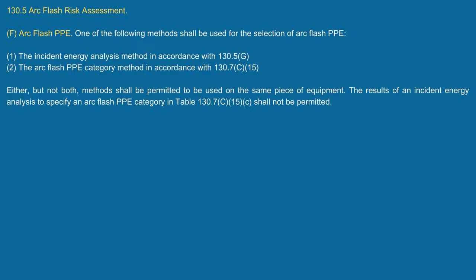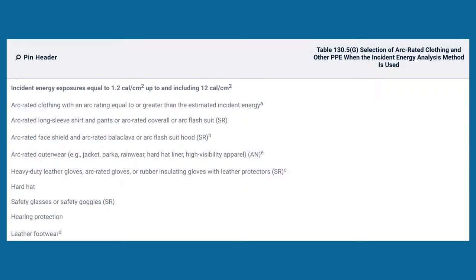Okay? Right. Now, if you look at this right here, this is where you get into Table 130.5 G. We used to have this over in Annex H at one time, and before that, we didn't even have the table, and people were complaining. So we put a table back there where you could go in and select your PPE. Now, once you get over 1.2 cal, that's what's considered a curable burn, a second-degree burn, and it says up to and including 12 cal, this is what we tell you need to have.